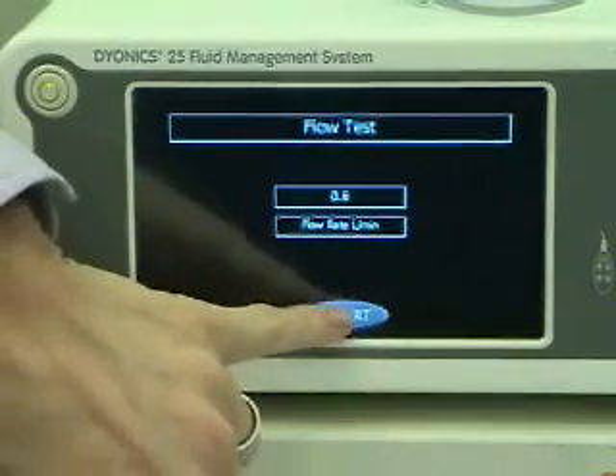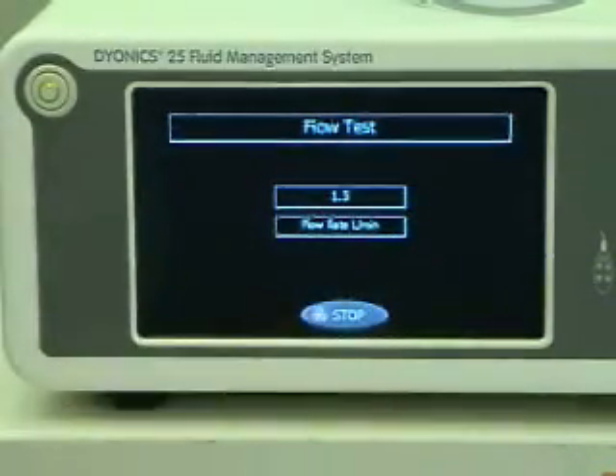If you then press the start button, the pump starts working, and the flow rate in this case has gone up to 1.5 litres a minute. So a way to calibrate the pump is to time 1 minute and collect the amount of fluid that comes out of the end, and to check the accuracy in 1 minute you should get 1.5 litres of fluid at this flow rate.